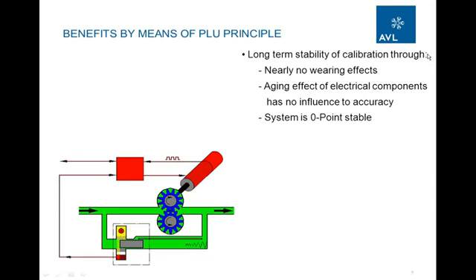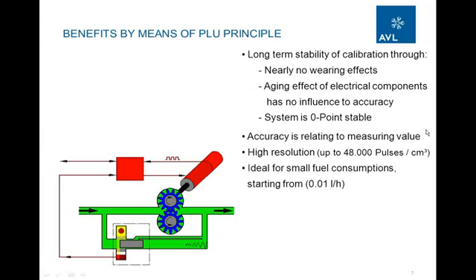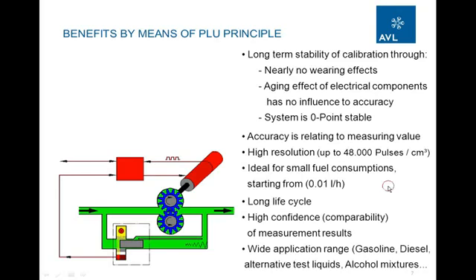With this principle, we have a long-term stability of calibration through nearly no wearing effects. Aging effect of electrical components has no influence on the accuracy, and the complete system is 0-point stable. The accuracy is relating to the measuring value, and we have a high resolution up to 48,000 pulses per cubic centimeter. And this principle is ideal for very small fuel consumption. We start at 0.01 liter per hour.